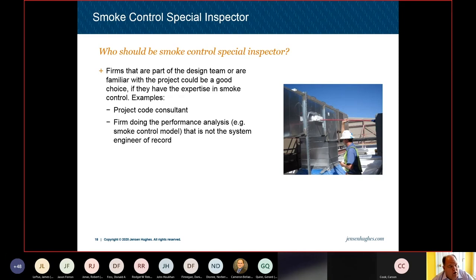What you want to do, though, is avoid the engineer of record. So if a mechanical engineer is doing the smoke control system as engineer of record, they have engineer of record responsibilities for the job that they're supposed to be taking care of. This smoke control special inspector is another person to oversee that stuff. And at the end of the day, not all smoke control special inspectors are created equal.